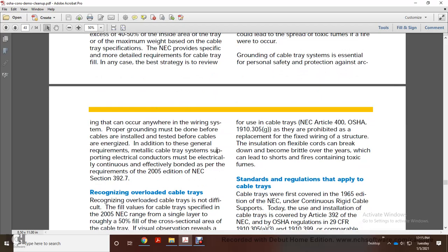Additionally, as a general requirement, metal cable trays supporting electrical conductors must be electrically continuous and effectively bonded, as part of the requirements of the 2005 National Electrical Code 392.7.